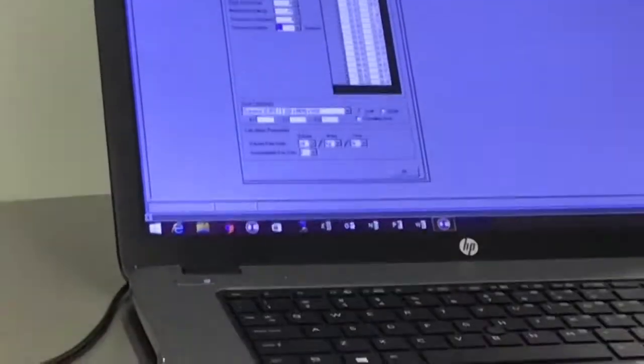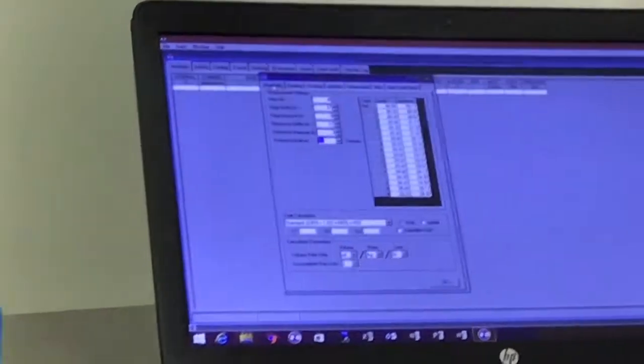So we measure cage 1, it gives us a number. Cage 2, you expect room air, but there's a little bit more CO2 than room air. That's how you know that little bit of CO2 came from cage 1 that didn't purge completely. At 15 seconds, you still get a tiny little bit from cage to cage. 17 seconds is completely purged.